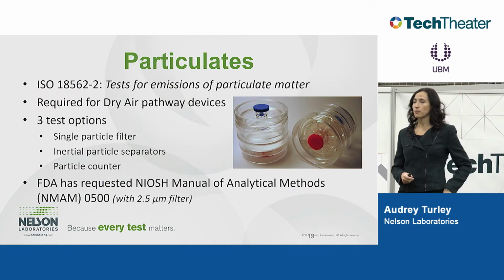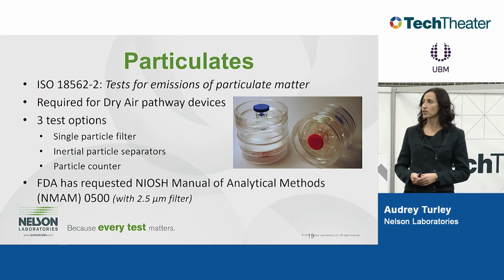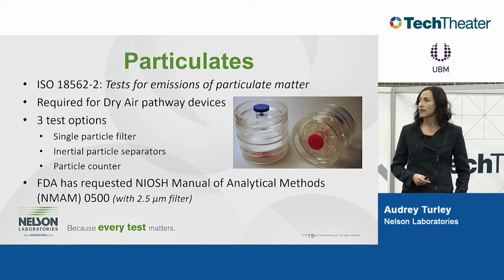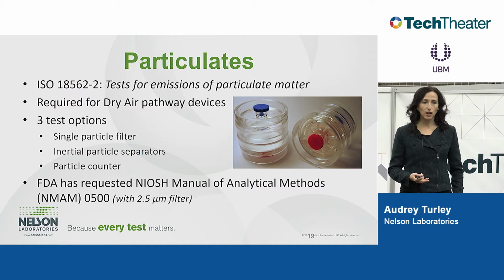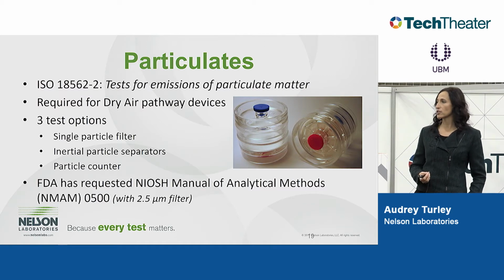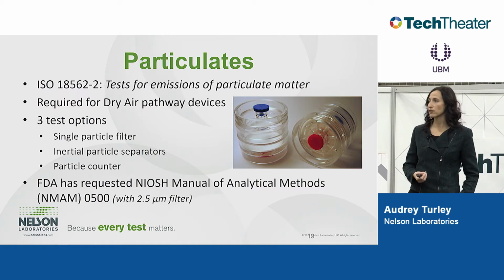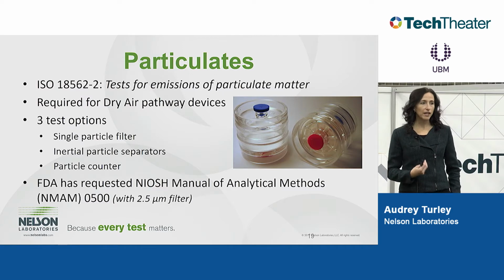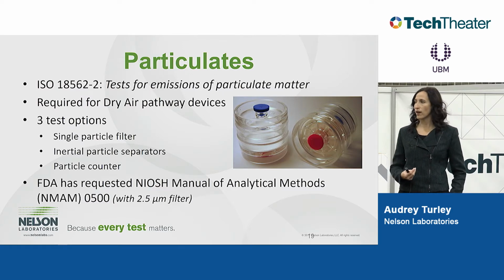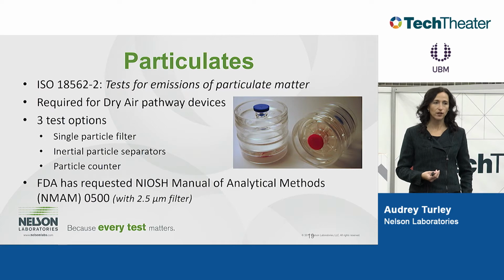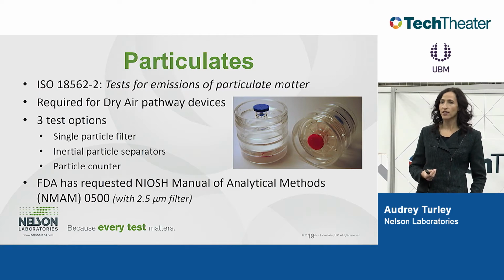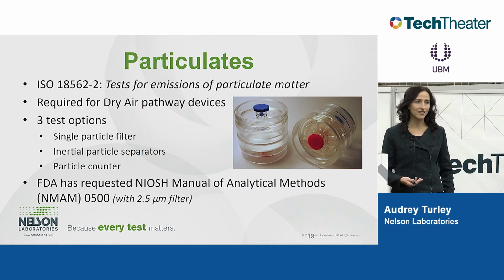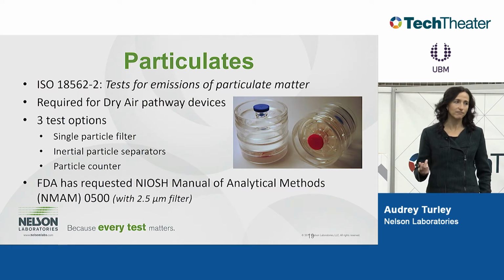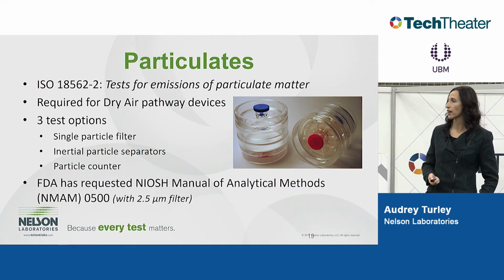So particulates, as part of 18562-2, are required for dry air pathway devices. The standard lists three test options: a single particle filter, inertial particle separators, and particle counters. We have had FDA specifically request the NMAM 0500 with a 2.5 micron filter—that's just been our conversations with them before. It's not listed as a requirement in the guidelines, but this has been the result of our interactions.